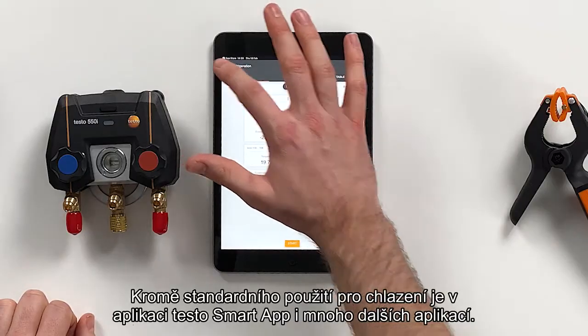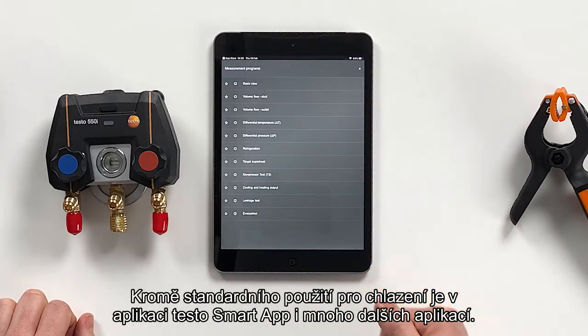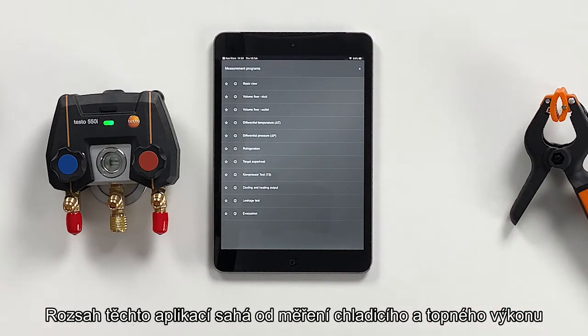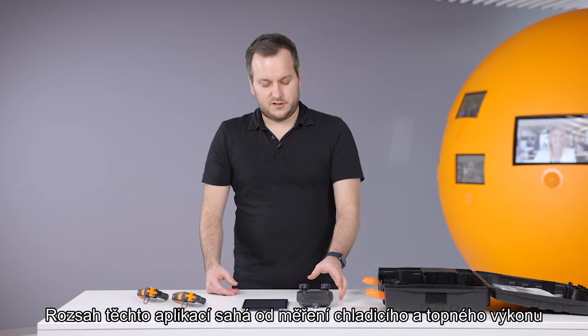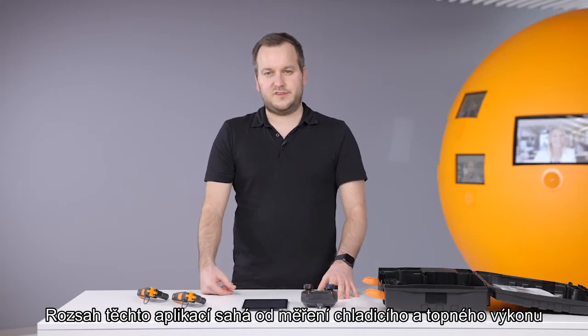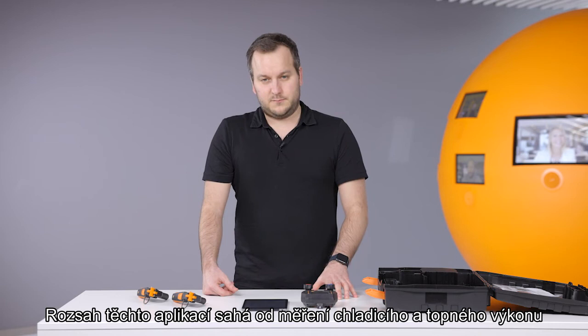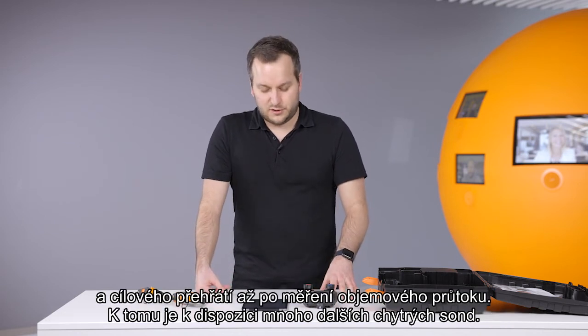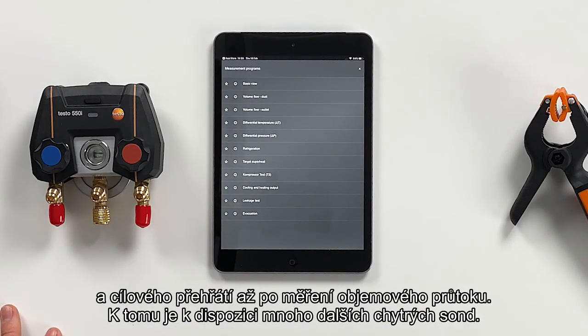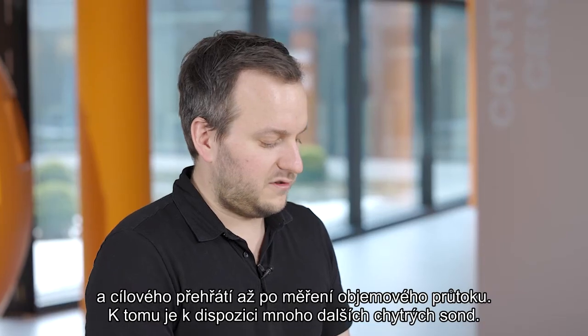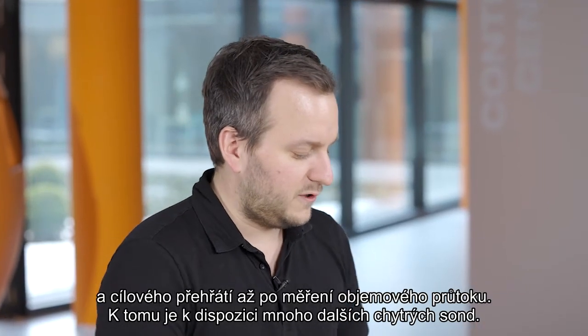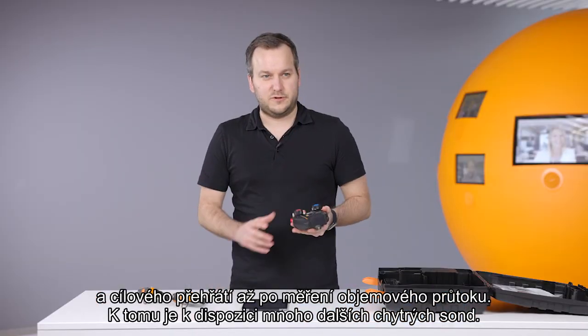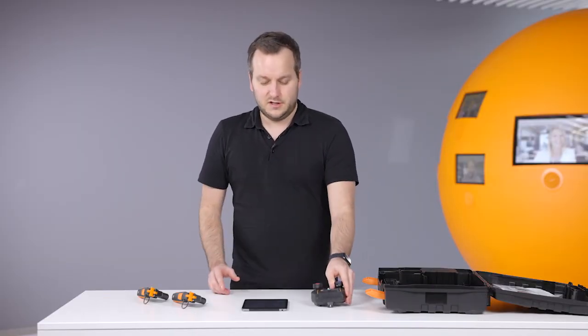In the smart app there are a lot of additional applications where you can use smart probes. For example, you can add probes for doing a target superheat measurement, or add volume flow smart probes to do a volume flow measurement. Everything is possible within this app, always at long range - the 550i, for example, has a range of over 150 meters via Bluetooth connection.